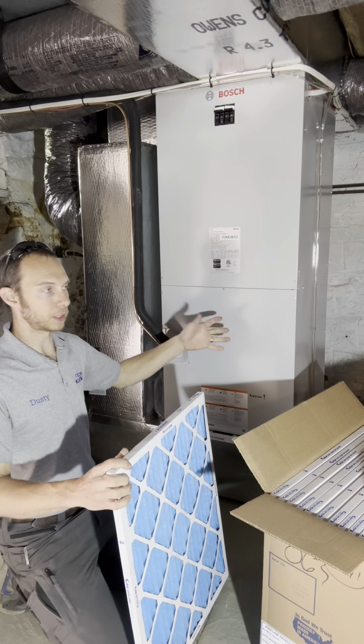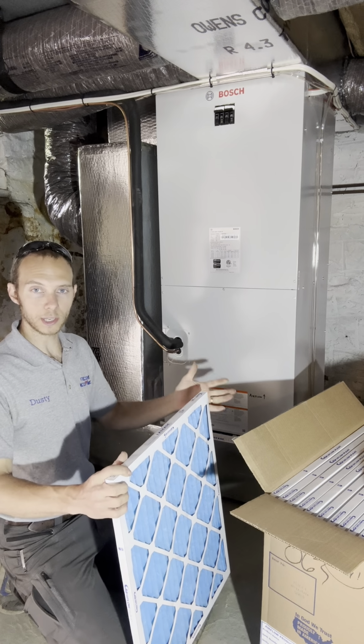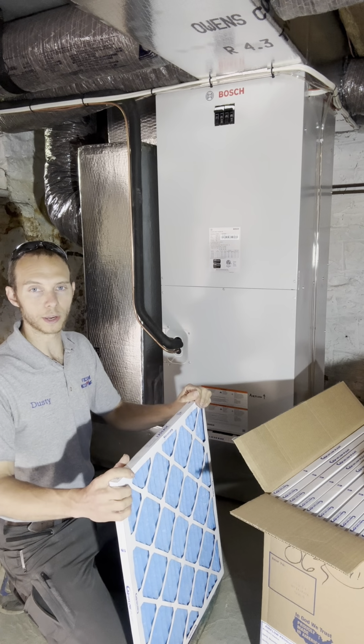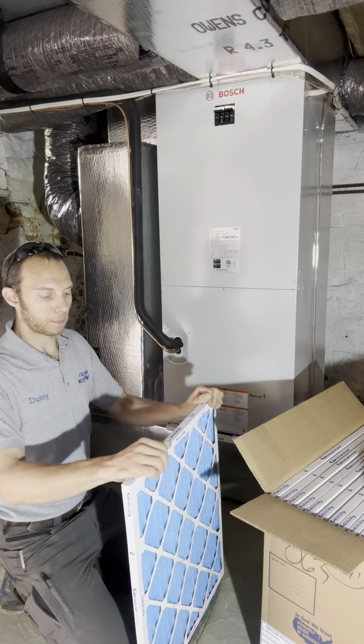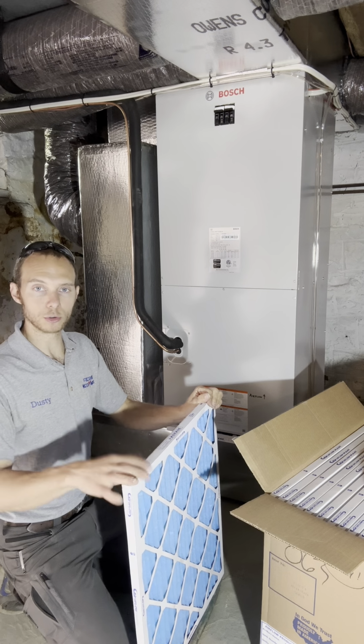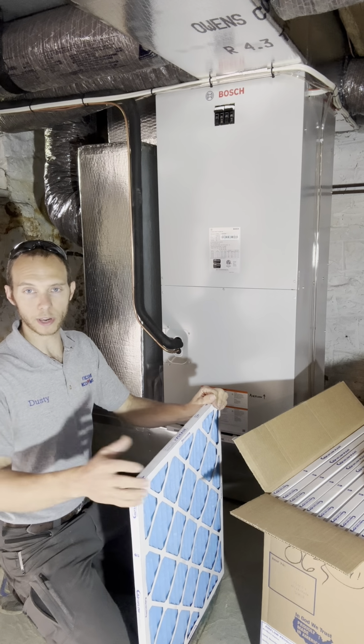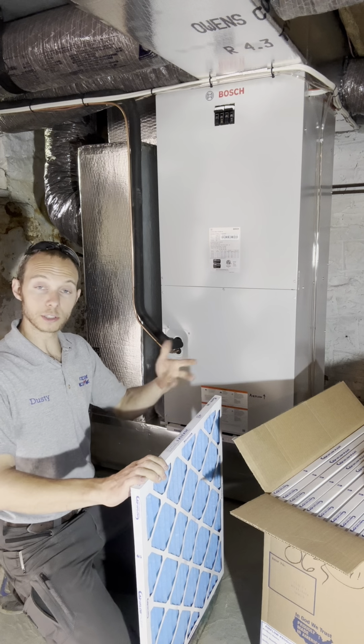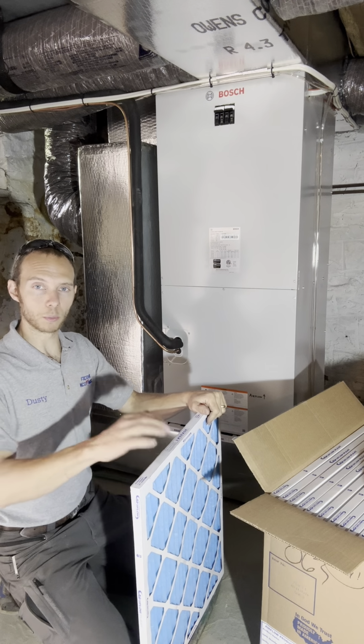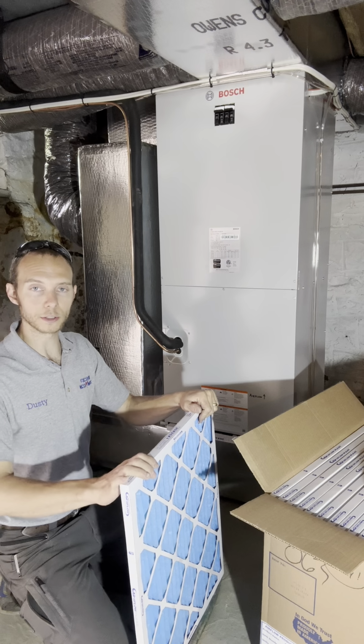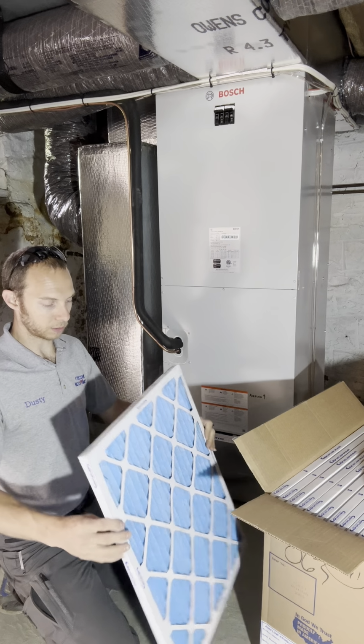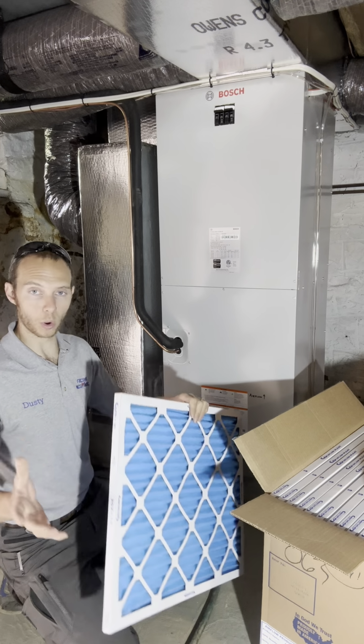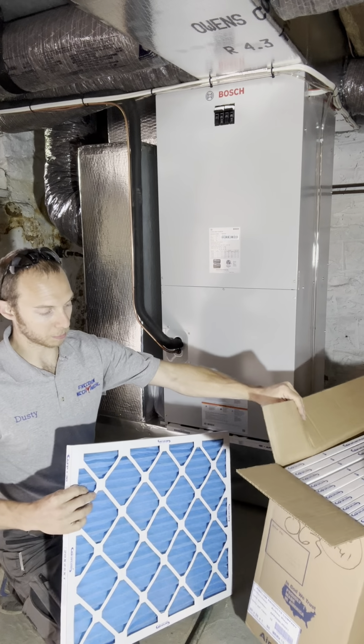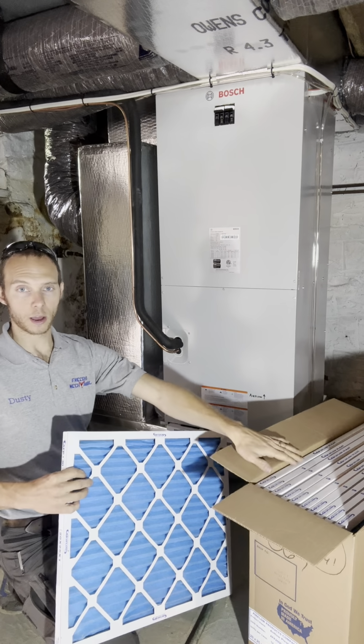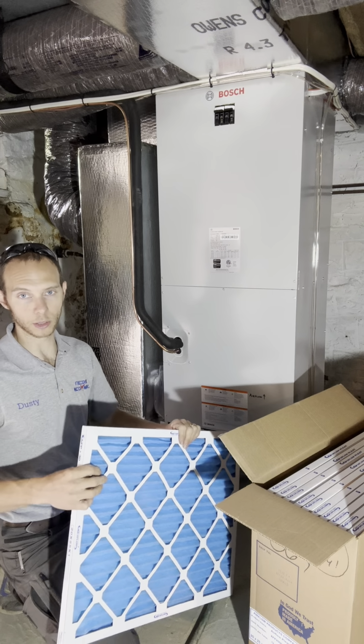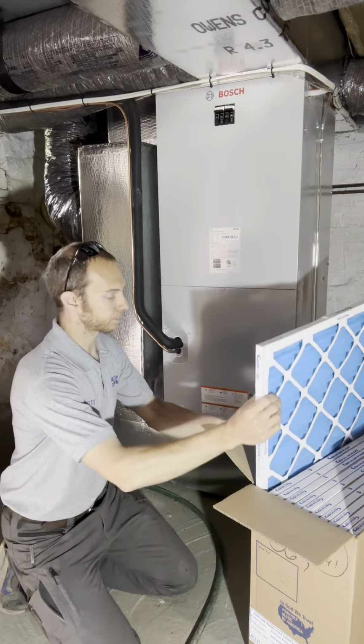This particular unit is oversized for the heating capability, so we have tons of blower there to help pull through. But MERV 10 is more than enough unless you run into a particular situation where you have allergies or you're noticing dust is still flying through the house. So then you might want to up to an 11 or a 13 or higher. So that's the number that we pay attention to as far as what you're putting in here. So we typically can get you better prices from our supplier than you can buy online or at Walmart or Lowe's or something like that.